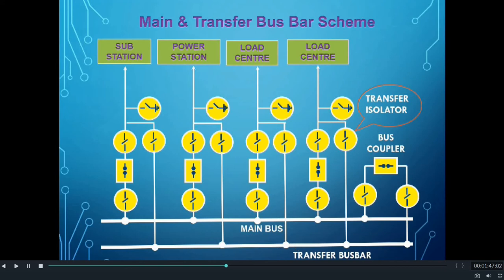The extra isolator used in the feeder for connecting to the transfer Busbar is known as the transfer isolator. Transfer isolators are connected in such a way that when a feeder enters the substation, it will face the transfer isolator first. In case of any fault or problem in the main switches of the feeder — that is, Line Isolator, Circuit Breaker, and Busbar Isolator — the feeder can be transferred to the transfer Busbar through this transfer isolator.